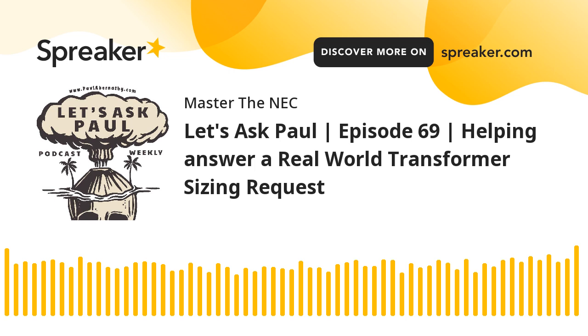So in our case, let's go through the pieces. Assuming we're going to terminate this into a single circuit breaker or a single set of fuses that limit that load, it says this single overcurrent device shall be permitted to supply any number of additional overcurrent devices. So like I said, you could feed a panel if you wanted.